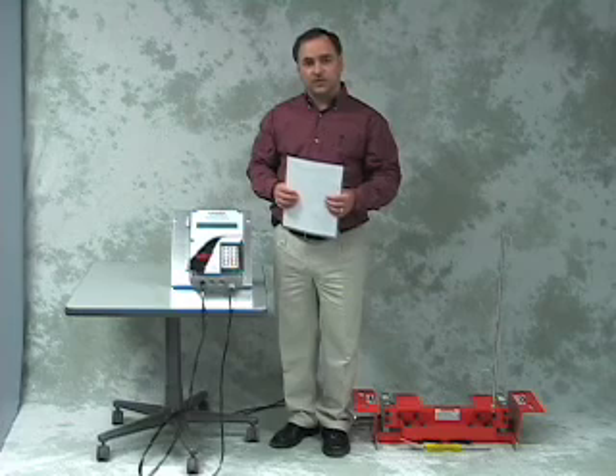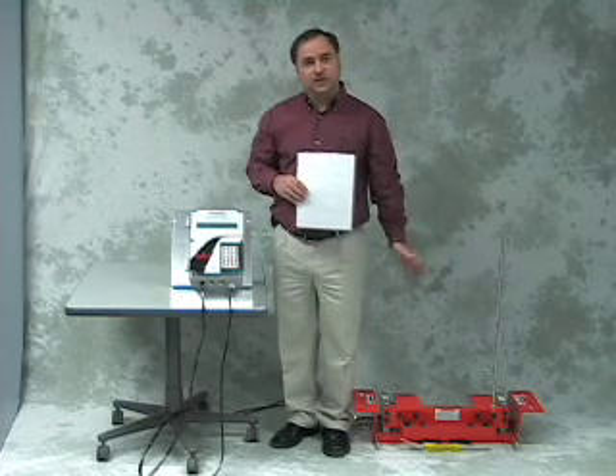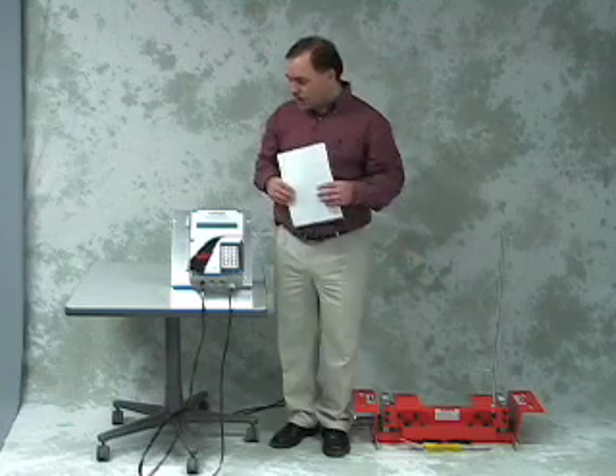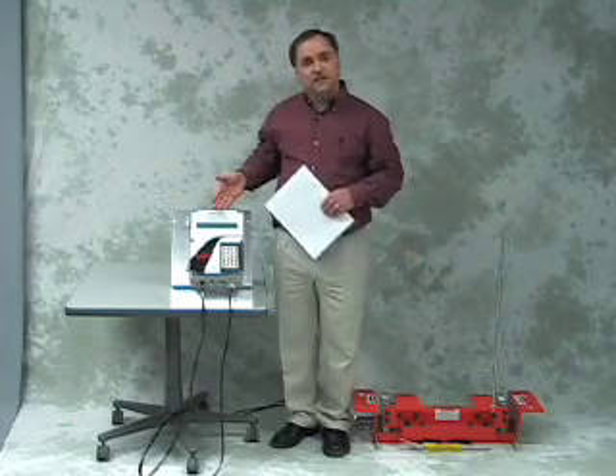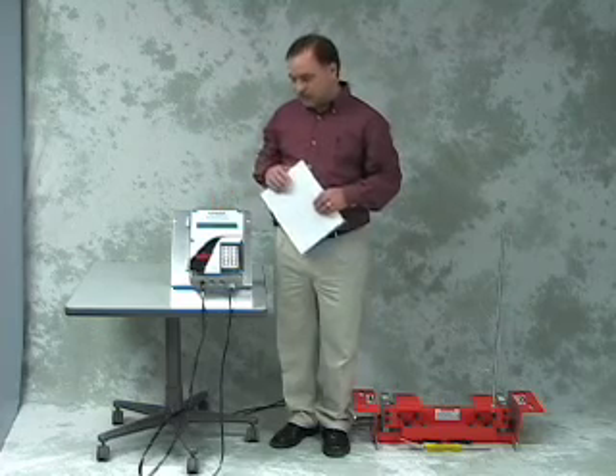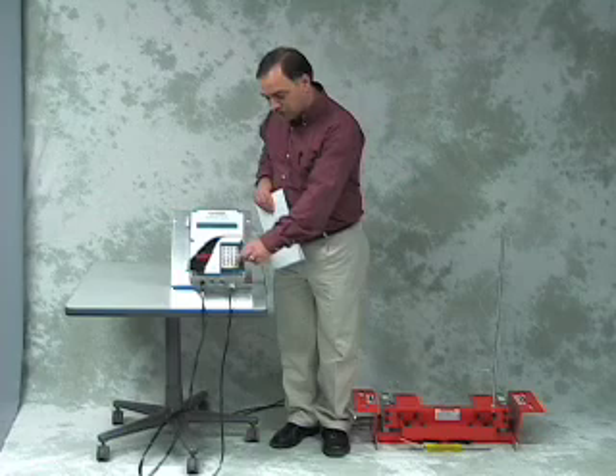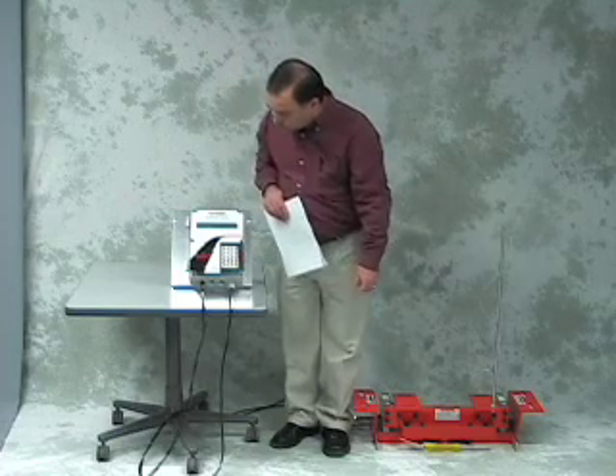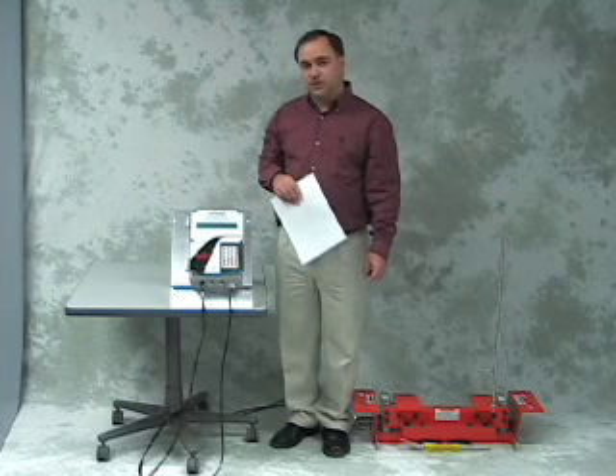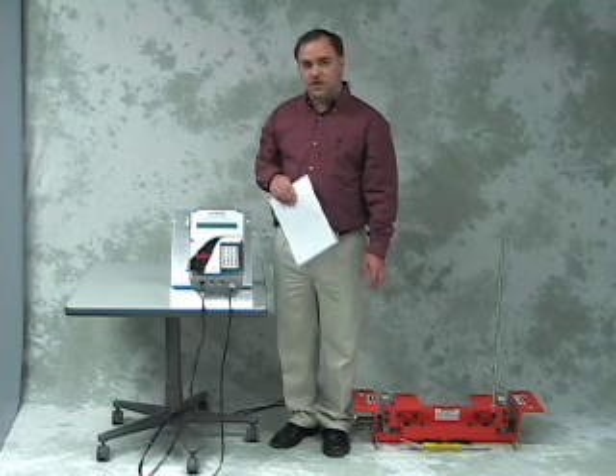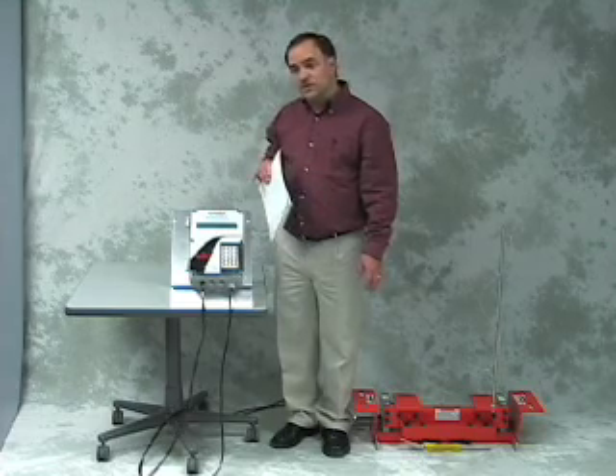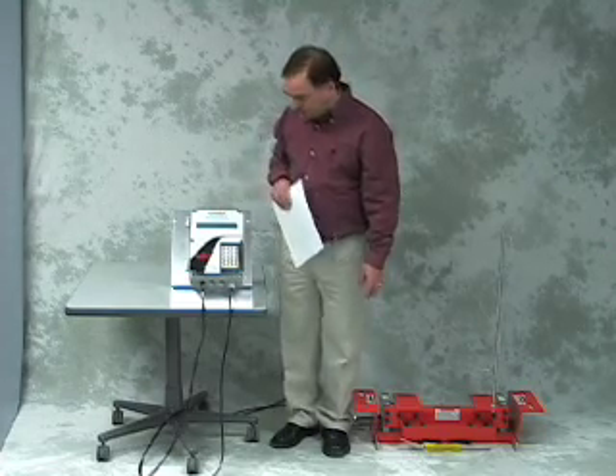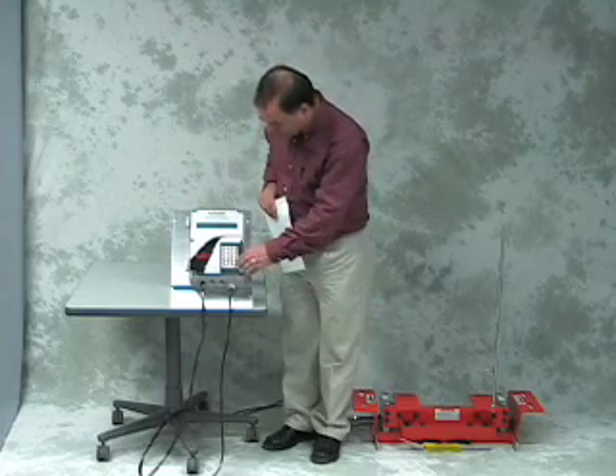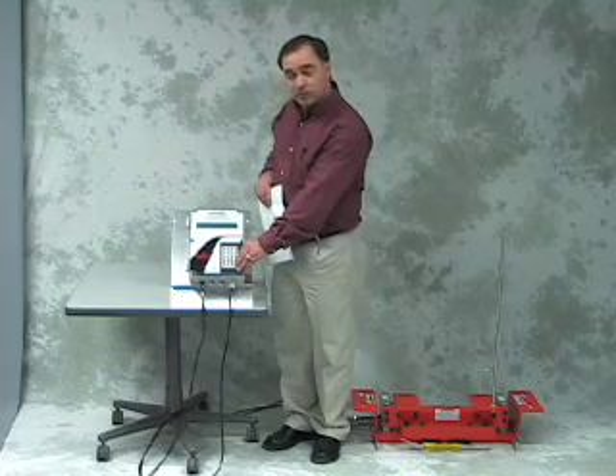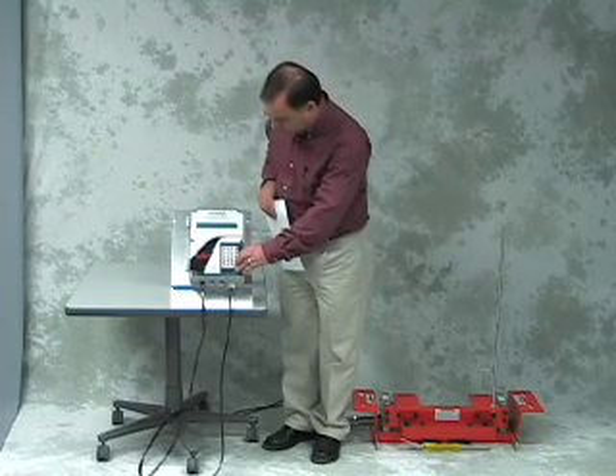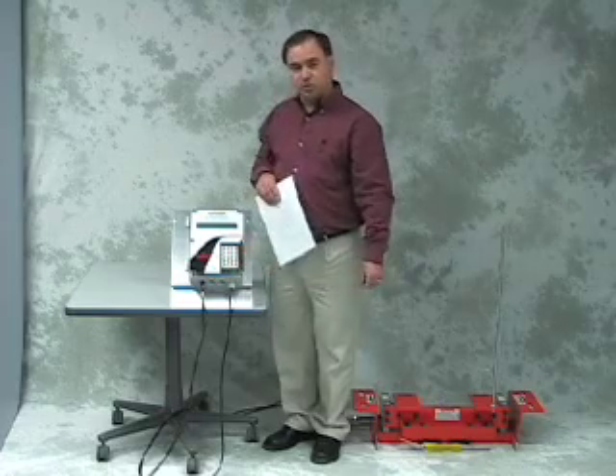Once you're ready to perform the demonstration in front of the customer, have the unit sitting and maybe not yet calibrated. Have the customer look at the display and see if it is reading 0. If it is not reading exactly 0, simply do a 0 calibration, 0 and enter, watch the display. With the calibration parameters that we have given you, the calibration should only take 3 to 5 seconds. So it's not a lot of time, but it's enough time for them to see that it is actually doing something on the display. Right now I'm displaying the 0 deviation. The calibration has been completed and there was no error. Press enter, press run, and we're back into run mode.